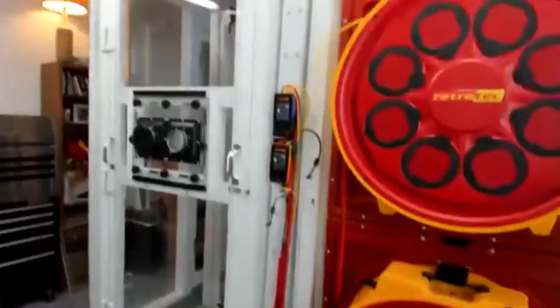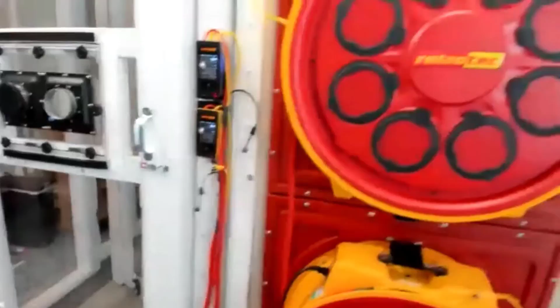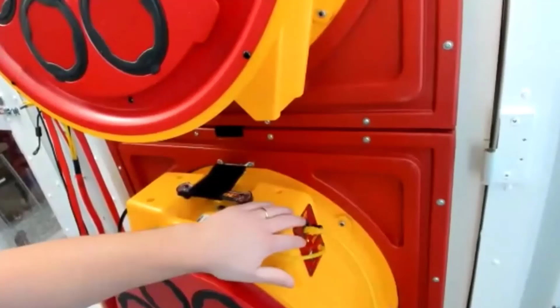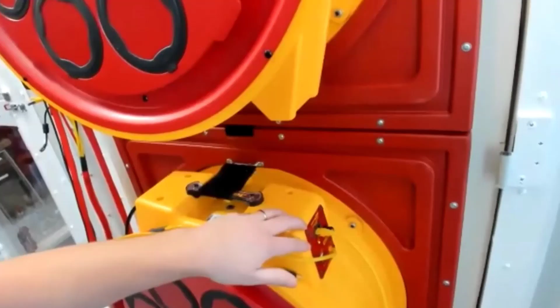So if this is my master gauge here at the top, it's got the Cat5 port going in to the fan. Then I have another cable coming in to my 5000 fan here. So this is getting a signal from the previous fan. So this fan is going to do exactly what the one before it is going to do. That way, they're spinning at the same rate at the same time. And if you notice, this other gauge is just kind of along for the ride. It's just collecting data from this fan.